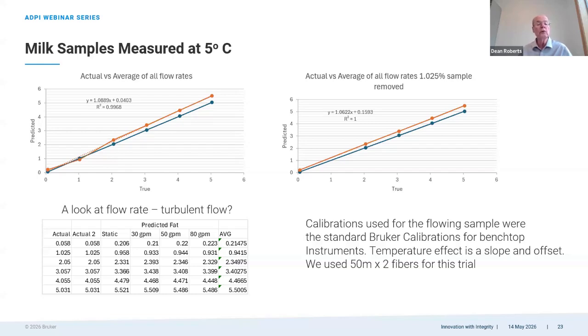But when we got up into the 2% and higher, it compared pretty favorably to the actual measurement. The 2% was a little bit high, and then we continued to be a little bit high. What we saw was a slope and offset. Our calibrations for the benchtop instrument are all measured at 40 C. So our conclusion was maybe the slope and offset is due to the temperature difference between the 5 degrees C and the 40 degrees C calibration spectra.